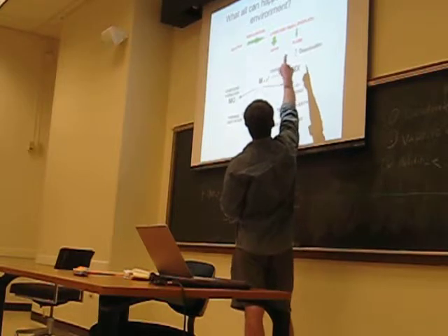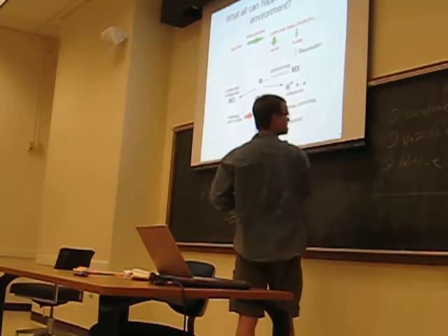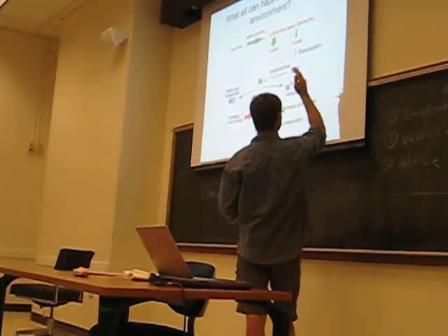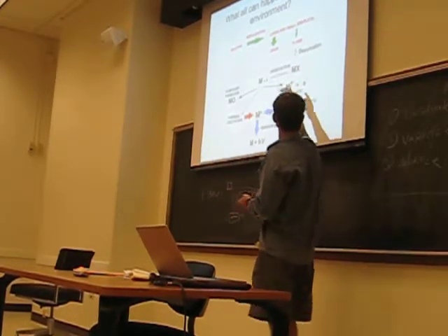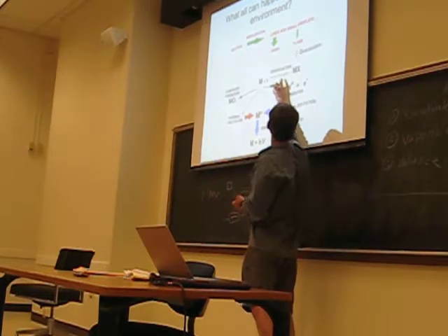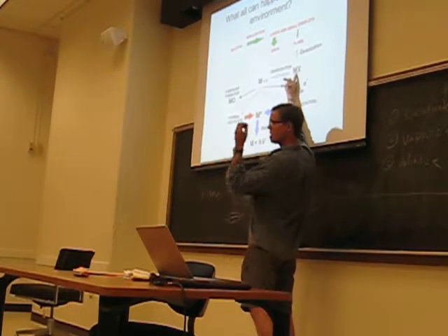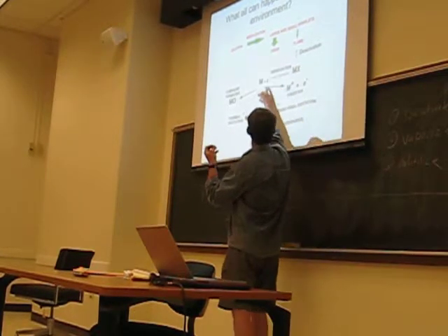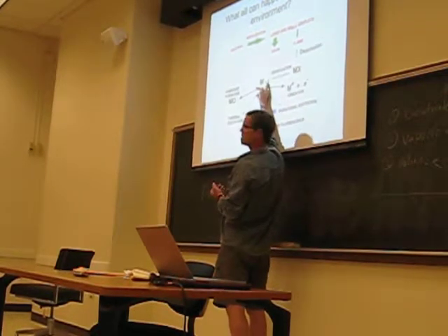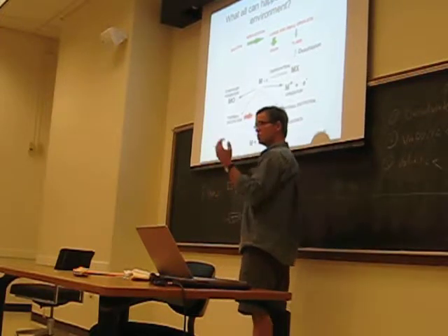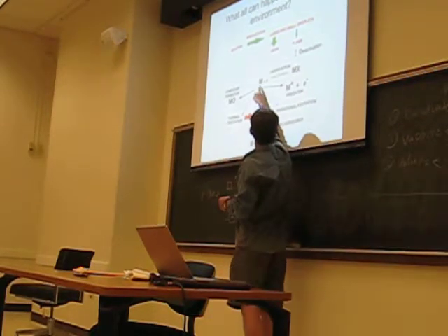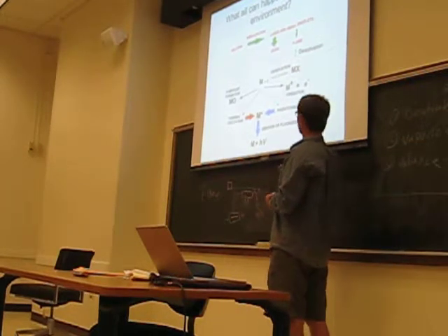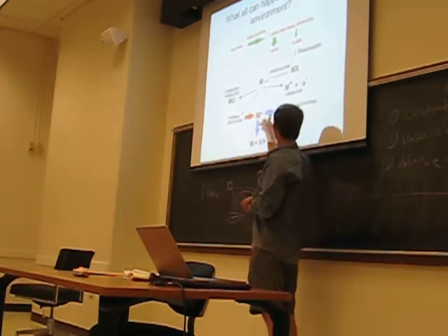Of that part that then enters the flame, it goes through those sequences that I mentioned here, where it's going to get desolvated, and vaporized, and volatilized, dissociated, where you're taking your metal complexes that are in a solid state in that flame thermal matrix, and it breaks them up into free atoms and whatever else is there, right? Now you want these free atoms to be available to be interrogated by your electromagnetic radiation to excite them and absorb that photon.